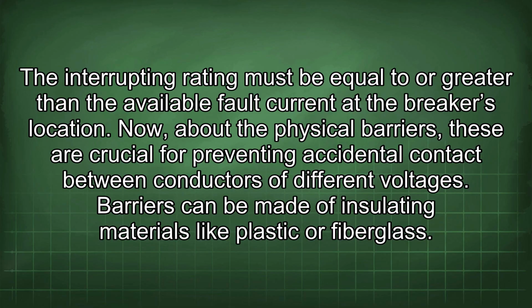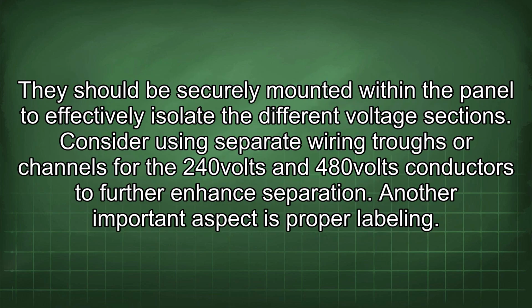Now about the physical barriers. These are crucial for preventing accidental contact between conductors of different voltages. Barriers can be made of insulating materials like plastic or fiberglass. They should be securely mounted within the panel to effectively isolate the different voltage sections. Consider using separate wiring troughs or channels for the 240 volts and 480 volts conductors to further enhance separation.